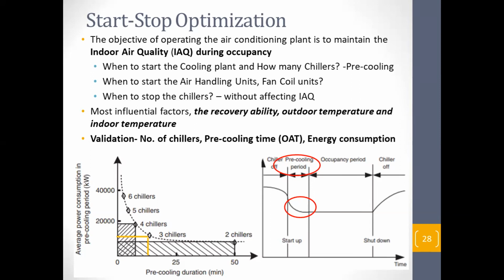The easy way is, there are 2 ways. One is that you can look at the chilled water return temperature and then decide when to start the second chiller. But the more professional way is to look at the outdoor temperature and prepare a chart. Assume that outdoor temperature is 32 degrees. How long will it take for your chiller system to bring down the temperature to an acceptable level by the time you have agreed to give air conditioning? Assume that you have agreed to provide air conditioning at 8 o'clock in the morning. By 8 o'clock, space temperature should be 24 degrees.